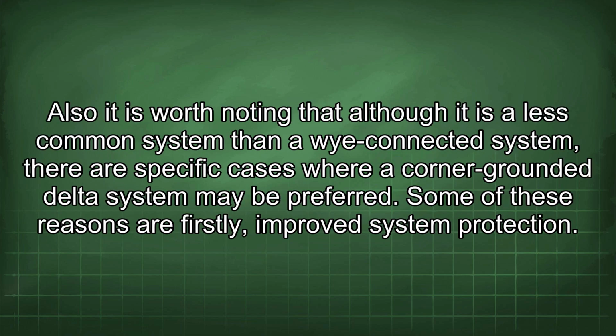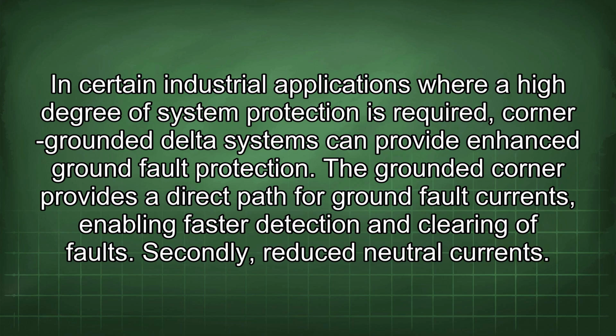Also, it is worth noting that although it is a less common system than a Y-connected system, there are specific cases where a corner-grounded delta system may be preferred. Some of these reasons are, firstly, improved system protection. In certain industrial applications where a high degree of system protection is required, corner-grounded delta systems can provide enhanced ground fault protection. The grounded corner provides a direct path for ground fault currents, enabling faster detection and clearing of faults.